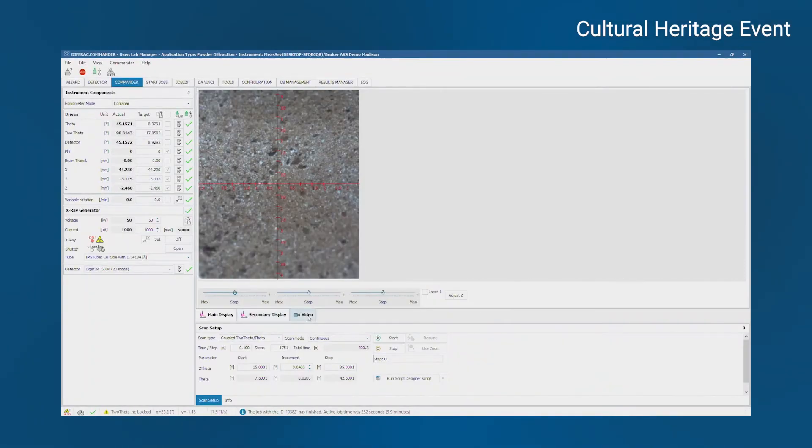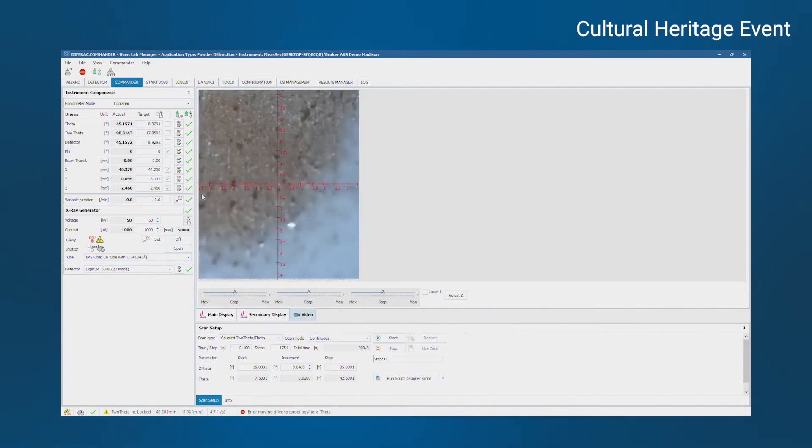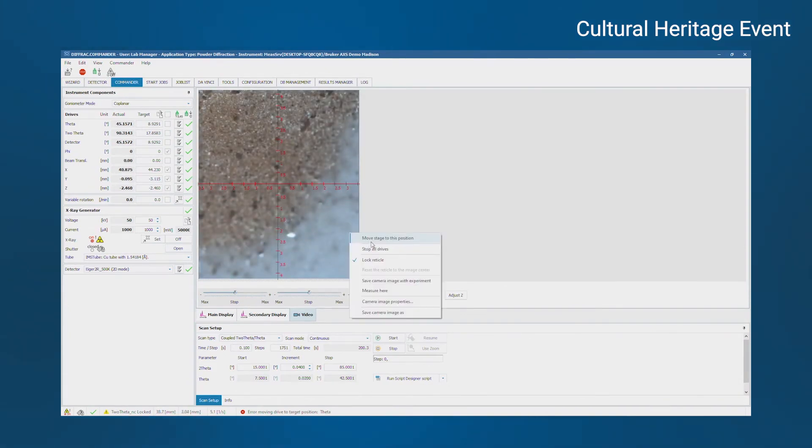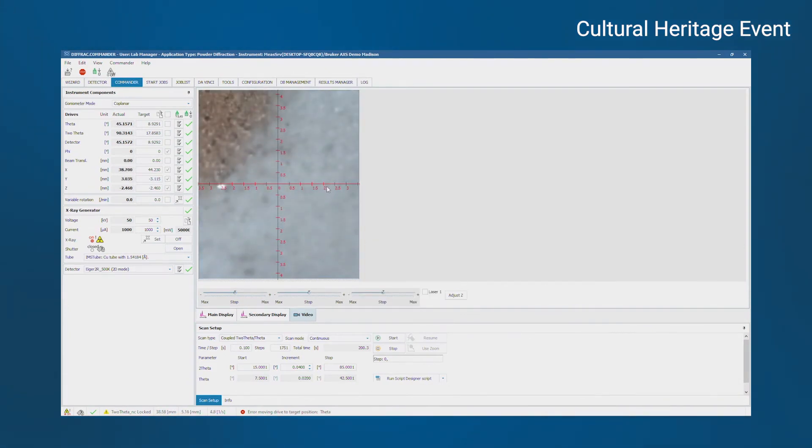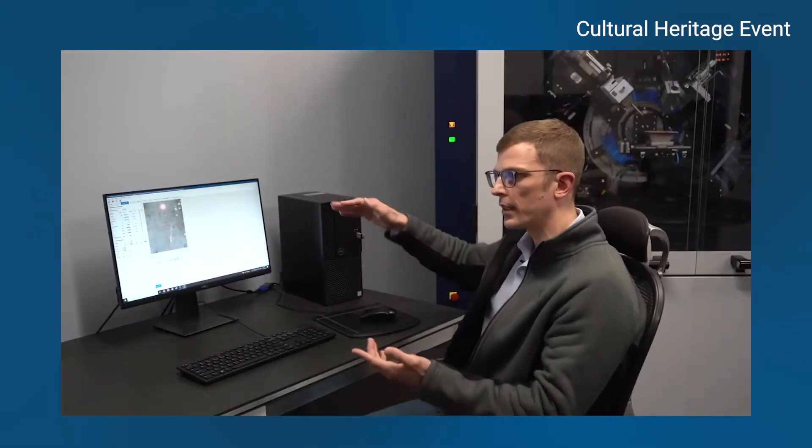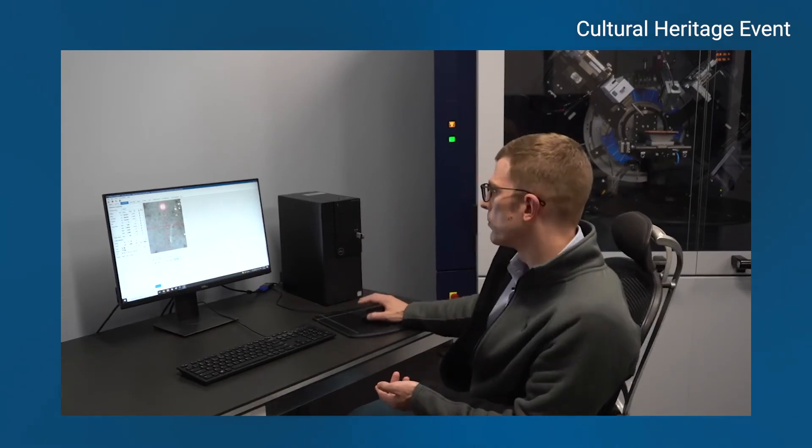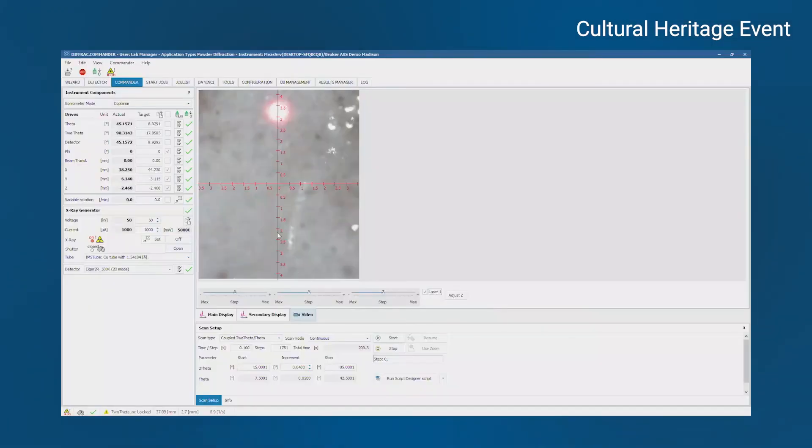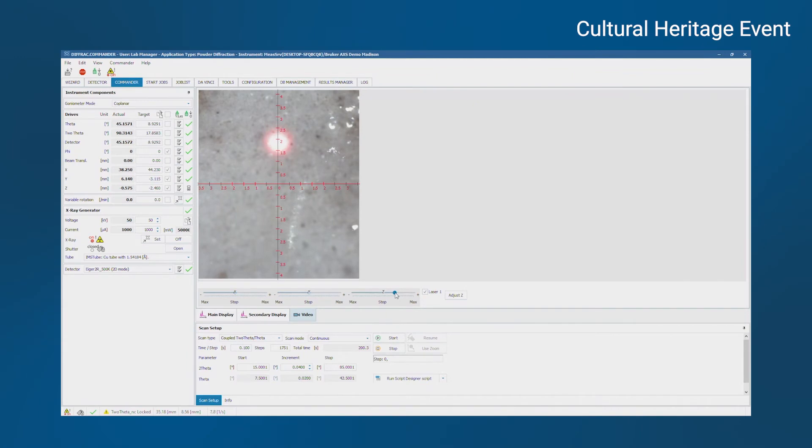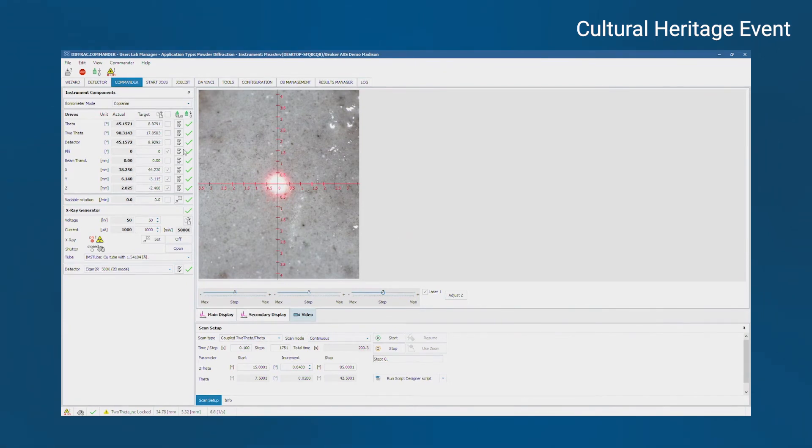So then what you might be interested in is, that's the bare ceramic. What if I measure the glazed area? Are there going to be any differences or not? And it's actually quite simple because you've already got the sample up and aligned. So all you do is click to move to this position till you get to a glazed region. This is a pretty good spot. Turn on the laser to make sure the sample height is right. This is a very non-even sample, so it's important to set the z height at every position. Click and hold the z slider until the laser is in the center of the camera image. And I overshot it a little bit, but that's pretty much it. So now it's centered. And just collect another scan.